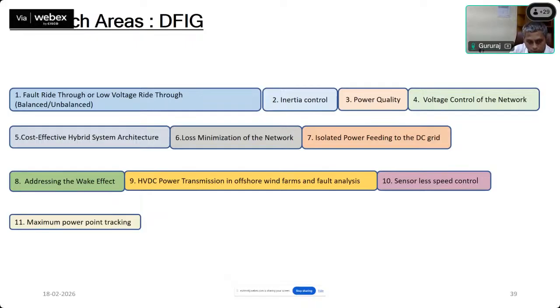During the isolated operation, the same grid side converter can be configured to push power from the wind power plant to the DC microgrid, so that we can improve the reliability. Also, the fault ride through can be effectively handled, because the DC microgrid has a super capacitor which helps reduce the burden upon the DC link capacitor, protecting it as well. So cost effective hybrid system architecture is becoming very popular, and industry is showing a lot of interest in this direction.